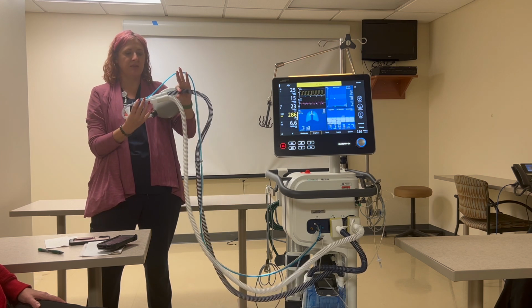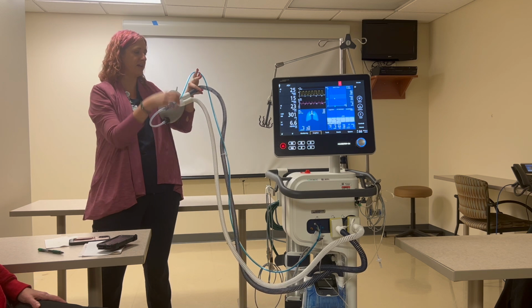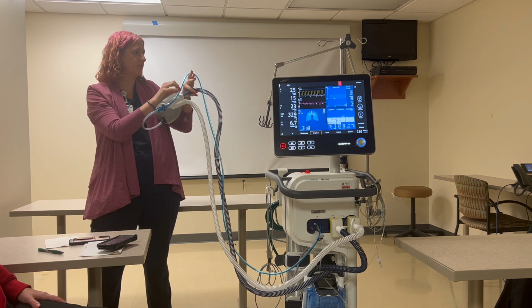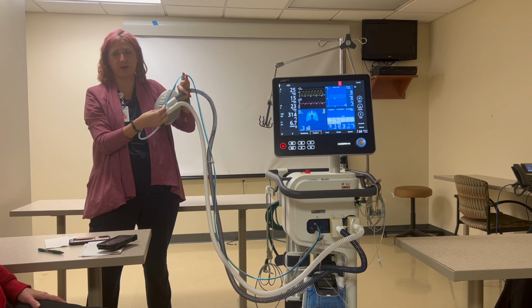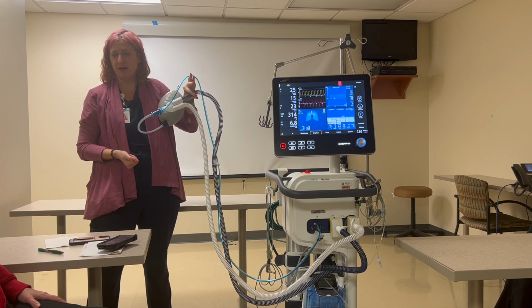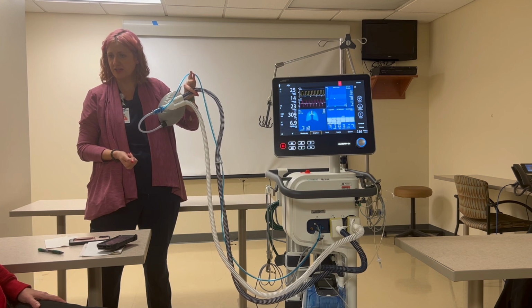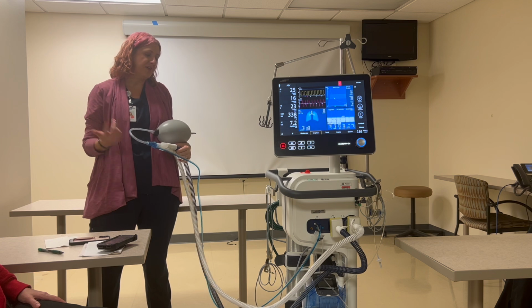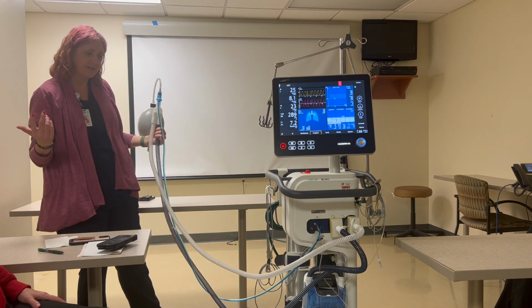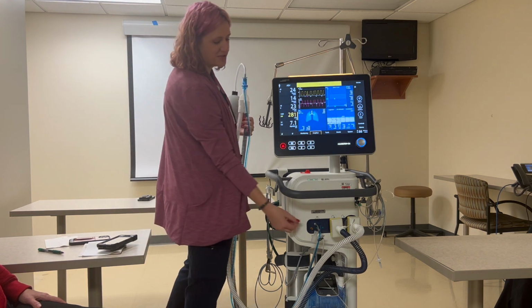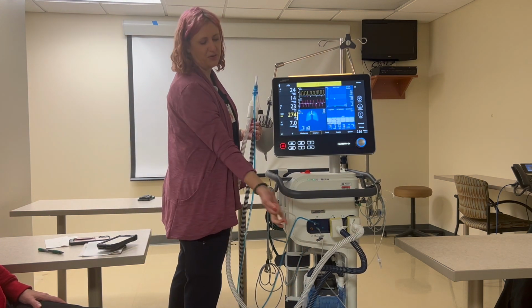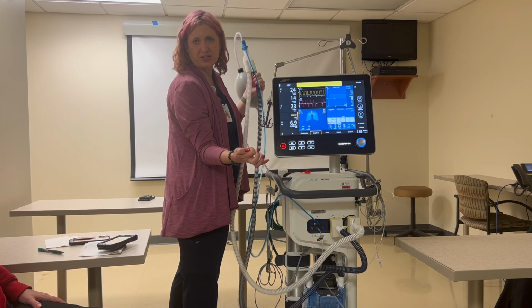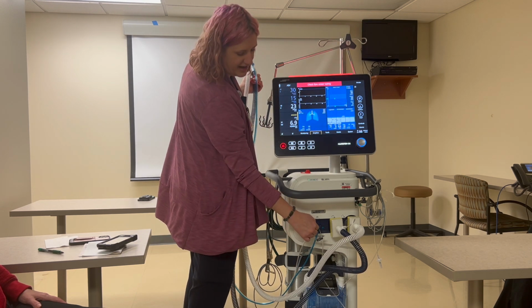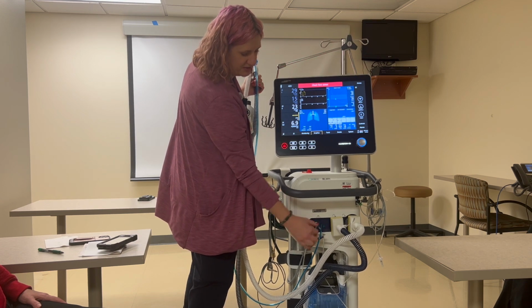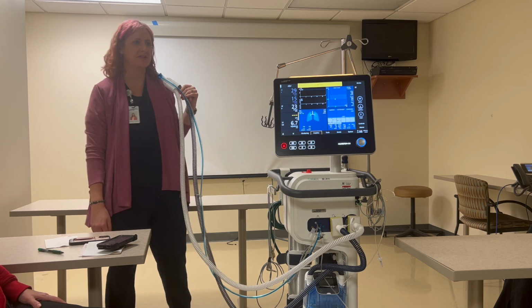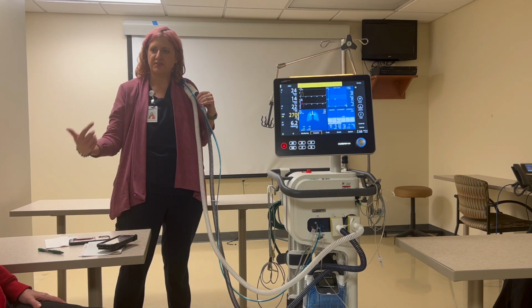All you have to do, again, put the flow sensor up at that 45-degree angle. There is always 2 cc's of flow going through this tubing, so it will flush that water or condensation back out. It just might take a minute or so depending on how drowned the circuit got. But no, let it do its thing. If RT is in the room or if you guys feel like doing this, it's my trick that I always use. You can disconnect the flow sensor tubing, hold it up to your flow meter, and the flow meter will flush out your flow sensor a lot faster as well. It's a hack that a lot of respiratory therapists will use whenever that end tidal ultimately gets drowned, because the end tidals are always gonna be drowned, so we use it so that we don't have to replace those devices.